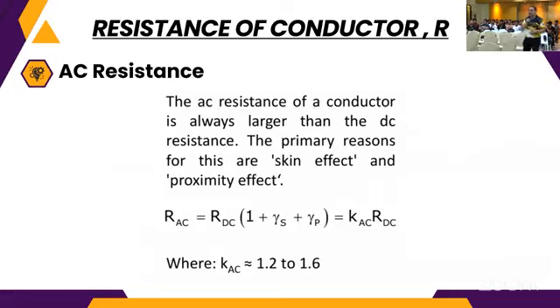Now, for the AC resistance of a conductor, we need to consider the skin effect and the proximity effect. So that's why the formula is: resistance in AC is equal to RDC, which comes from the formula resistivity times length over the area, times 1 plus the skin effect plus the proximity effect. So we come up with the constant K AC times RDC, where K AC is approximately 1.2 to 1.6. Okay, next.